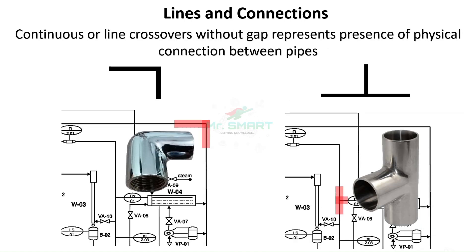The next important thing to notice in a P&ID is the lines and connections used in it. Lines are used to define many things that we need to understand. A thick continuous line in a P&ID represents pipeline connections. Wherever you see a straight line connecting some equipment or instruments, it shows they are connected with a pipe physically. Continuous lines or line crossovers without a gap represent a physical connection between pipes. If you notice a line shaped like an L or T in the drawing, they are denoting an L-bend or T-joint to be made at those points physically.